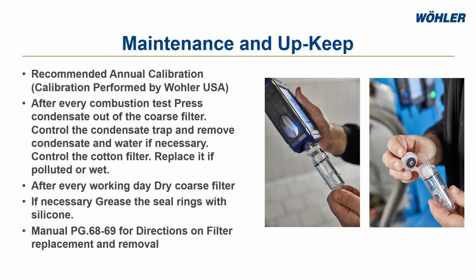For example, here's some pictures of the A450. As you can see, you pull the water trap out there, remove the water stop, and then the dust filter sits right below that water stop. So you can pull it out, put a new one in, pop the water stop in, and twist your water trap back into your analyzer. It's really simple. And the design on the A450s make it so that the upkeep and maintenance that you would do there on your own is fairly simple.